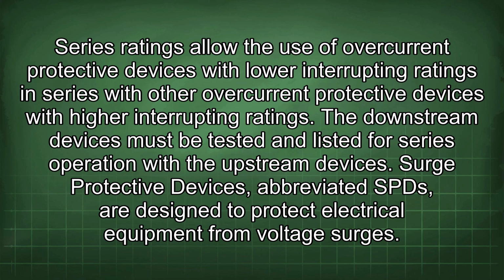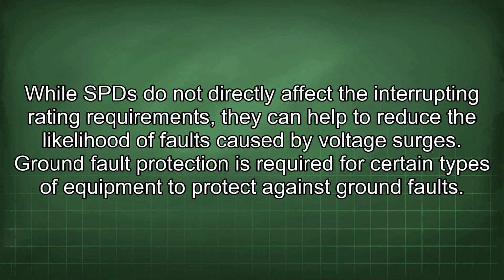Surge protective devices, abbreviated SPD, are designed to protect electrical equipment from voltage surges. While SPD do not directly affect the interrupting rating requirements, they can help to reduce the likelihood of faults caused by voltage surges. Ground fault protection is required for certain types of equipment to protect against ground faults.